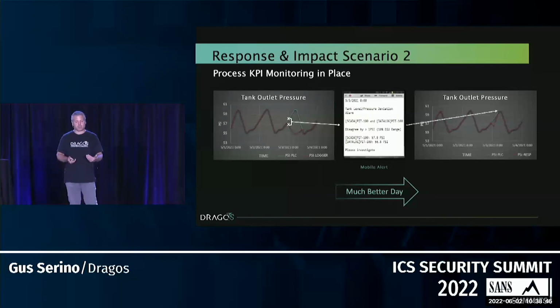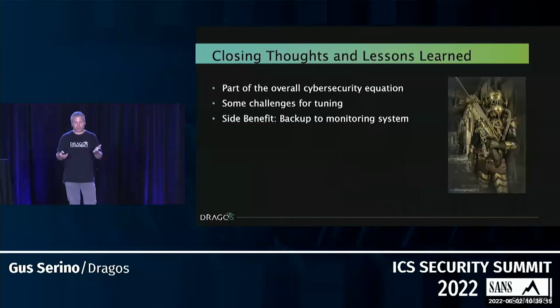When the pumps stop, as soon as the deviation passes a certain threshold, you get that differential between what the data logger is saying and what the SCADA system is telling you. They can send an alert and say, hey, we better go check this out. Sure enough, there's a problem. Let's kick in our emergency operating procedures, start those pumps, and start filling the tank. And now we're dealing with just a cyber problem, which is enough, and not a physical problem at the same time. My hope here is to present an idea of using what you have, not necessarily cybersecurity technology, to help build a resilient system. Situational awareness is not the be-all and end-all, obviously, but it's a good tool to have in the tool belt.